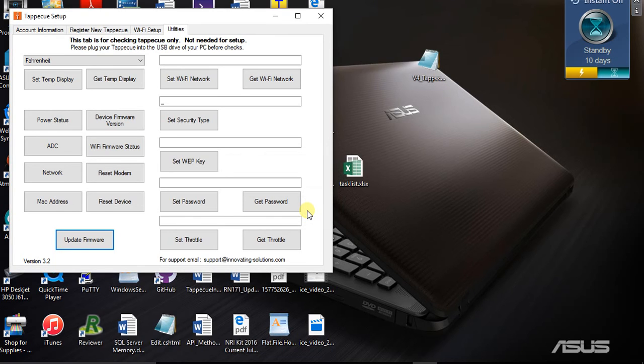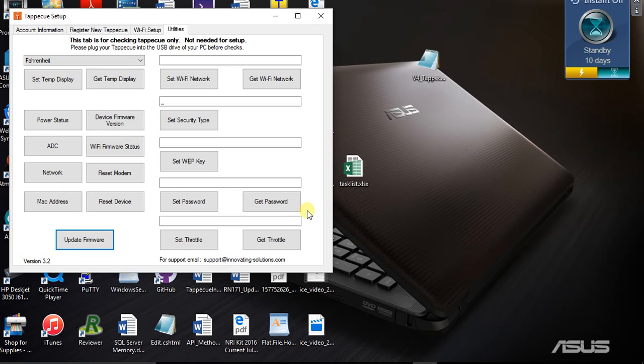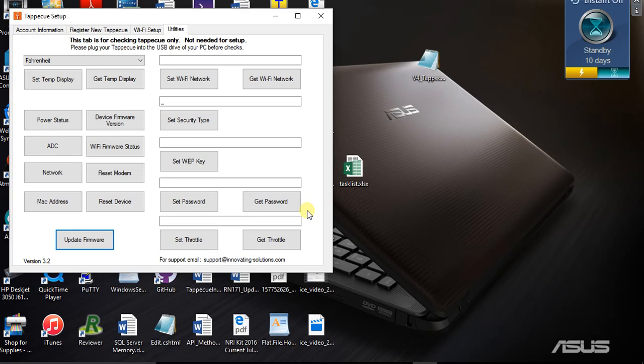Now you're going to wait for it to show PC connected again on your LCD, which mine does now. If it does not show PC connected and it shows low repeatedly or it shows temperatures, then what may be the problem is that you didn't have a probe plugged in before you plugged it into the PC. So just unplug the Tappecue, plug a probe in, and then plug the Tappecue back into your PC again.